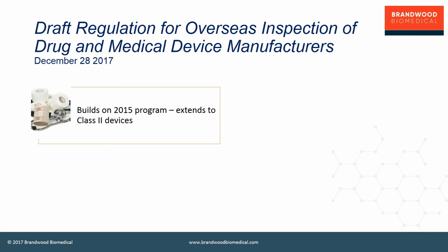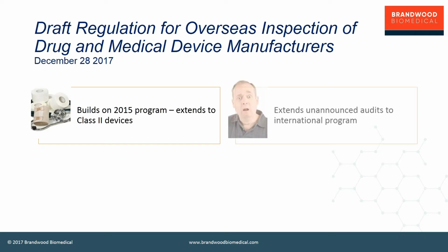And what does it do? It builds on the existing program. In 2015, CFDA started doing international inspections, but those were few and far between, and only done on manufacturers of the very highest risk implantables. Now this new program extends to all class 2 devices as well as class 3s, so it's a much more broadly based program in terms of the devices covered and the manufacturers to be audited.